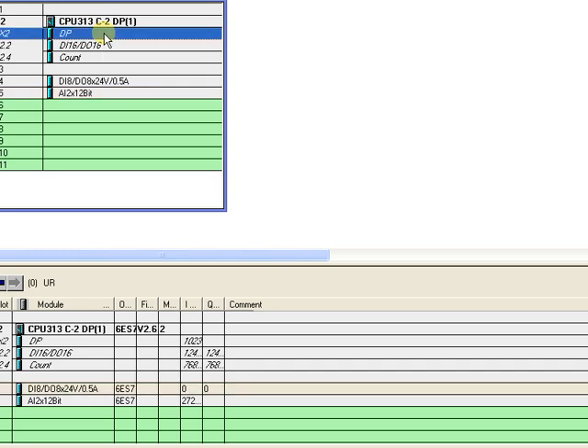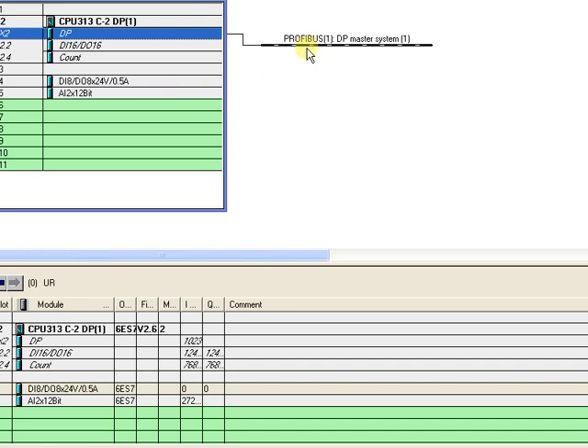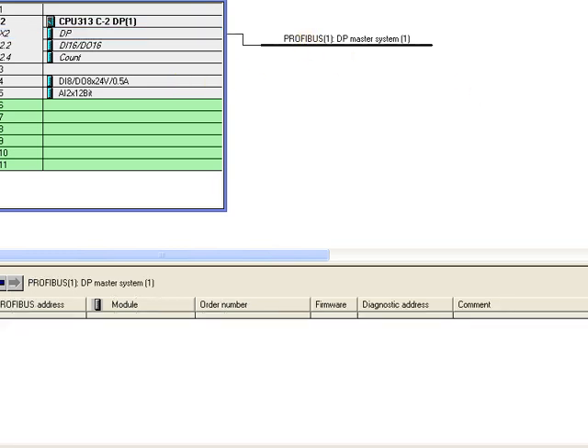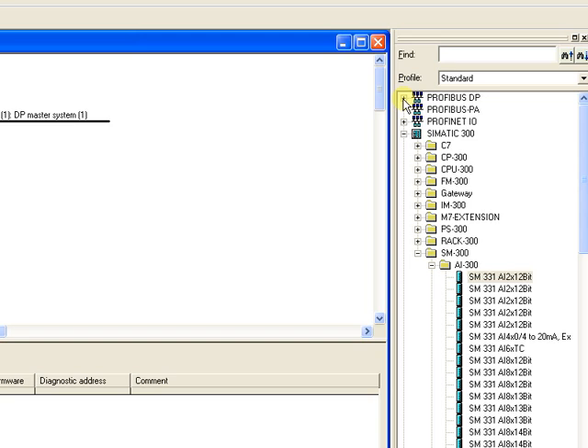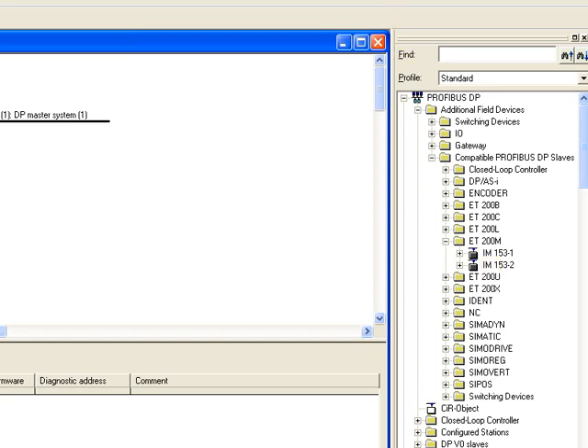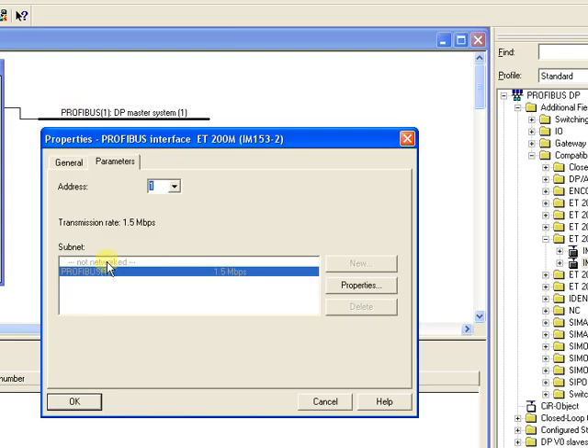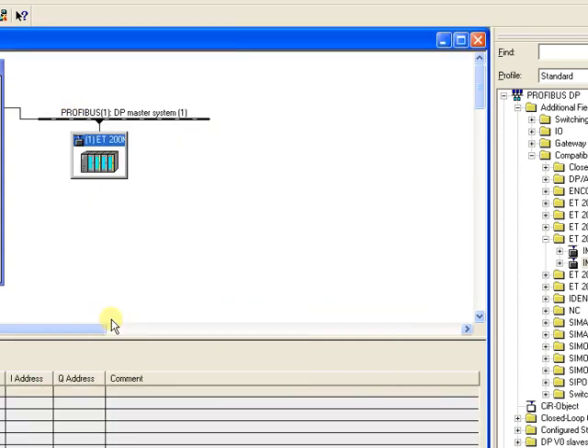For adding PROFIBUS, right-click the DP, click Add Master System, and your PROFIBUS is added. To add Unit 1 and Unit 2 with the PROFIBUS system, click on PROFIBUS DP, then click Additional Field Device, then click on Compatible PROFIBUS DP, then ET200, then the IM module. Drag and drop it into the PROFIBUS and click OK. Your module is now attached to the PROFIBUS system.